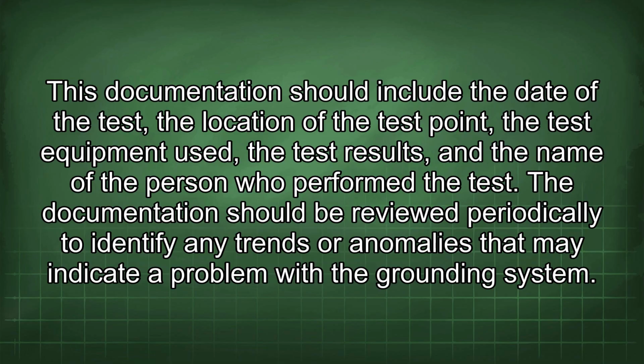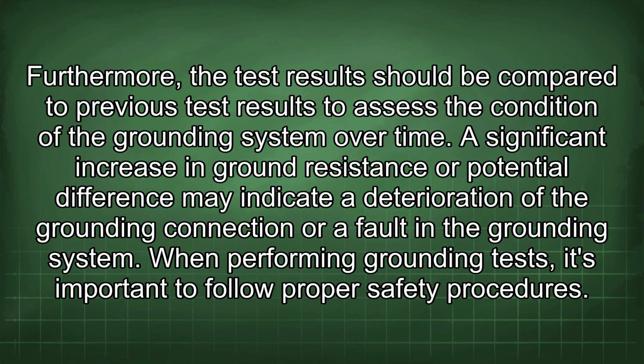This documentation should include the date of the test, the location of the test point, the test equipment used, the test results, and the name of the person who performed the test. The documentation should be reviewed periodically to identify any trends or anomalies that may indicate a problem with the grounding system. Furthermore, the test results should be compared to previous test results to assess the condition of the grounding system over time. A significant increase in ground resistance or potential difference may indicate a deterioration of the grounding connection or a fault in the grounding system.